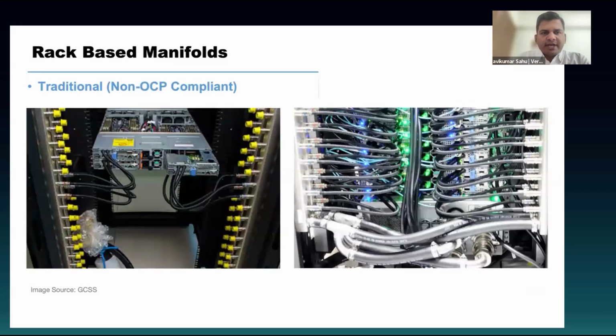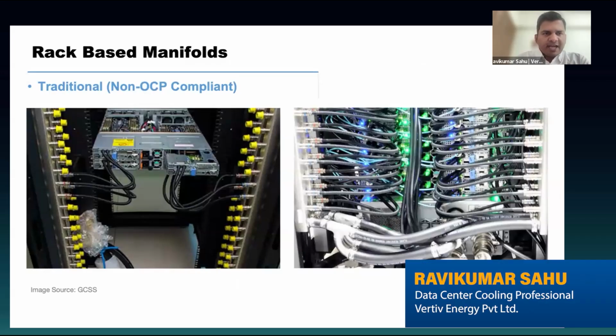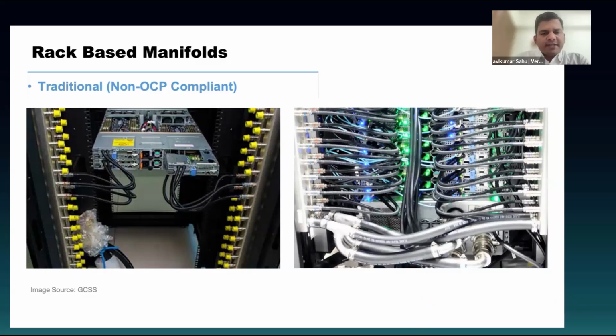So this is your manifold. A manifold is a mechanism or pathway for how the cold fluid goes into the cold plates and comes back. This is one of the critical components. In designing this system, your flow and your pressure inside this rack-based manifold are very critical. From the design point of view, your flow, your temperature, your pressure, everything depends here. So this is a very critical part of direct to chip liquid cooling.